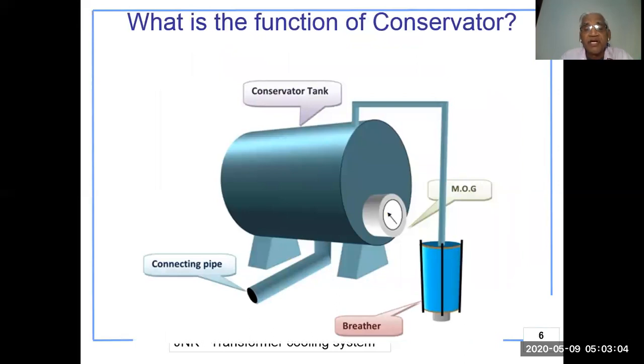From the conservator, the bottom connecting pipe goes to the transformer for communicating with the oil, and the top pipe comes out going to the breather. The breather is filled with silica gel, and the conservator also has a MOG (magnetic oil gauge) which shows the oil level.